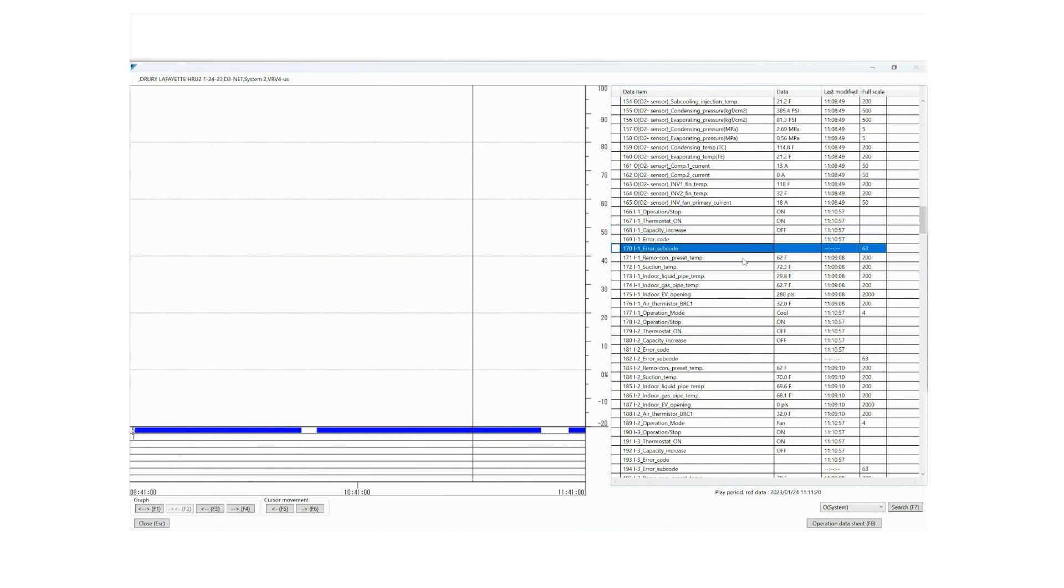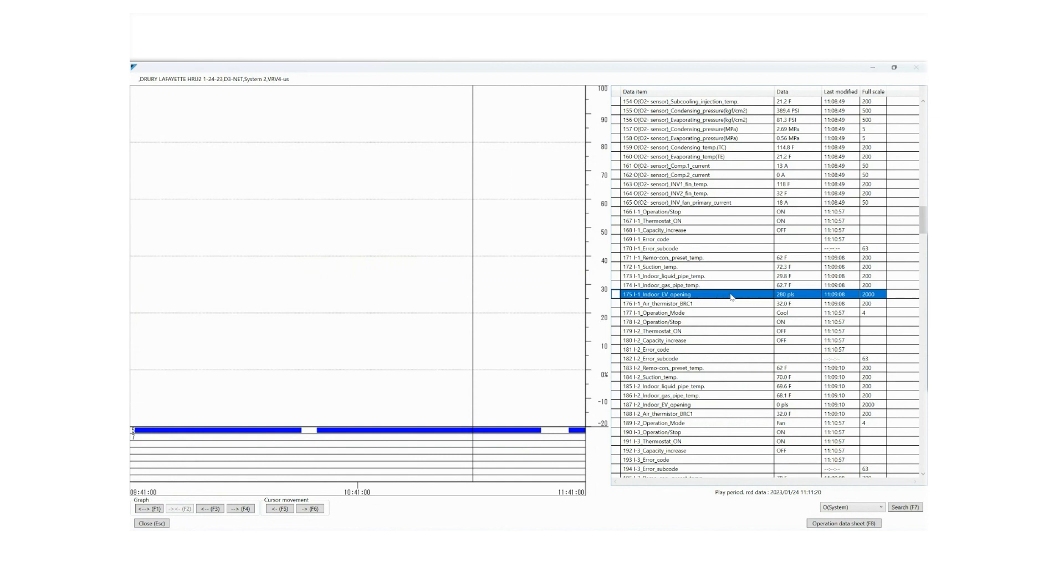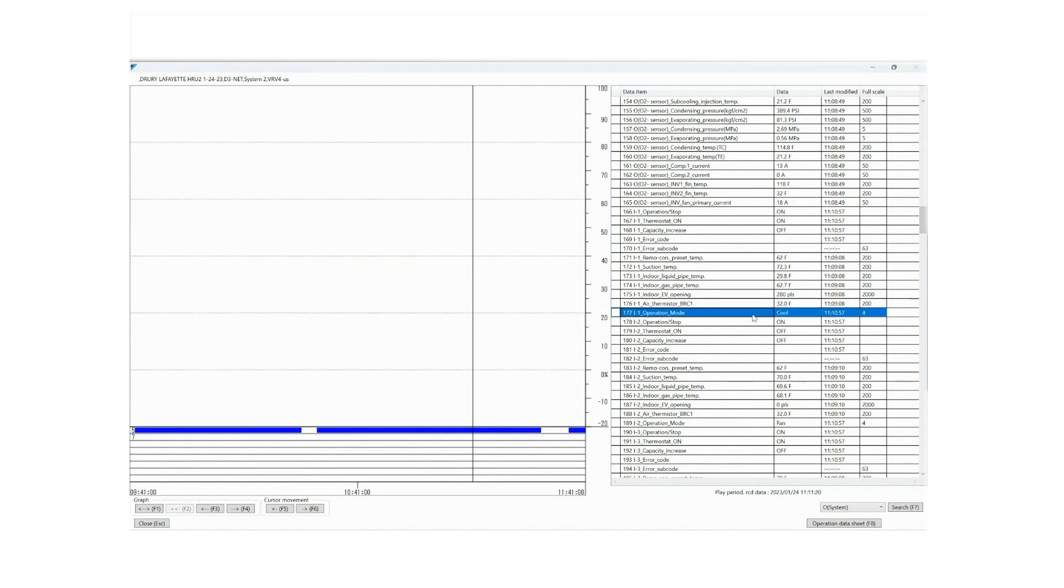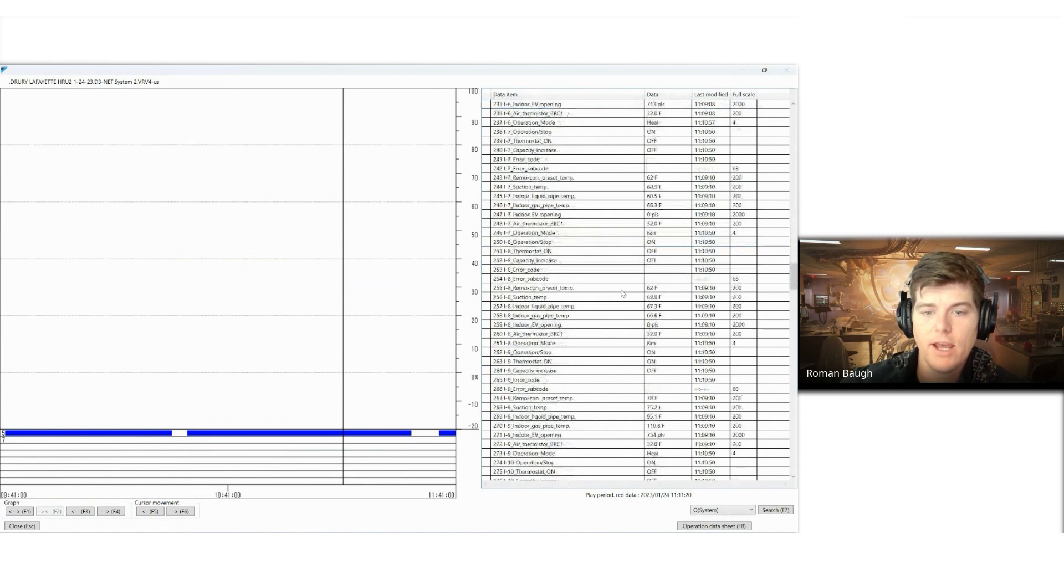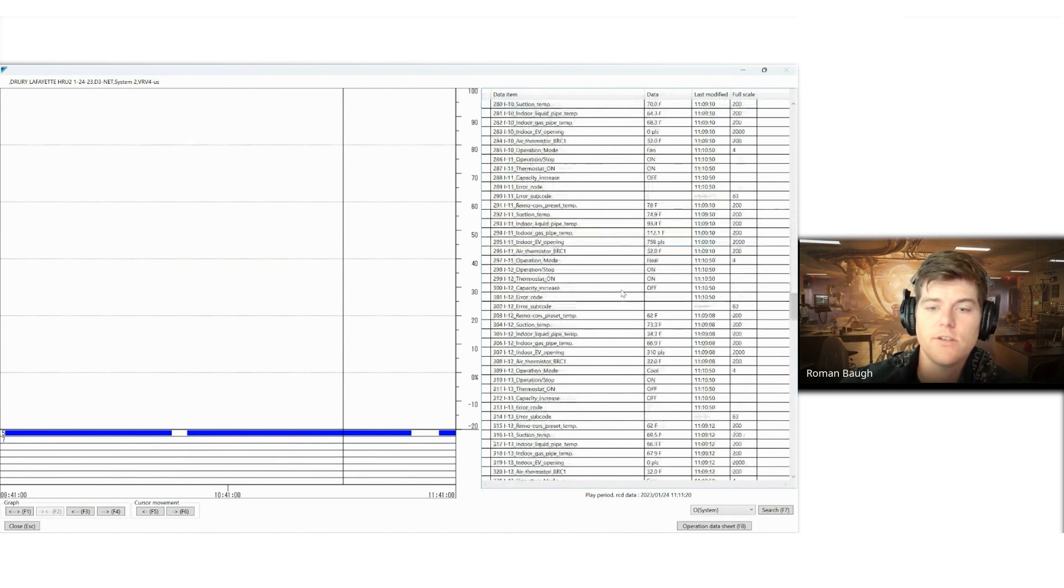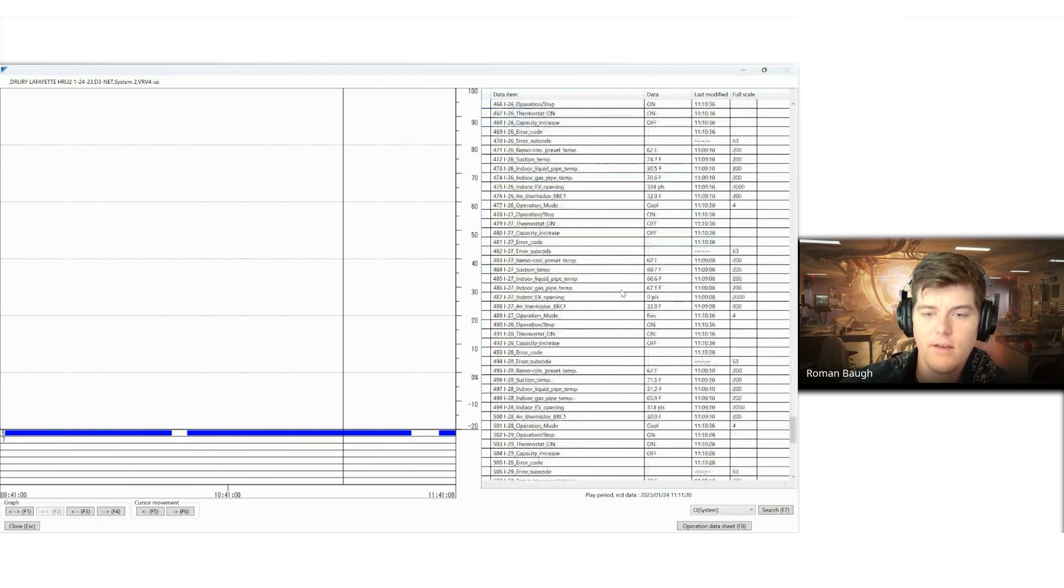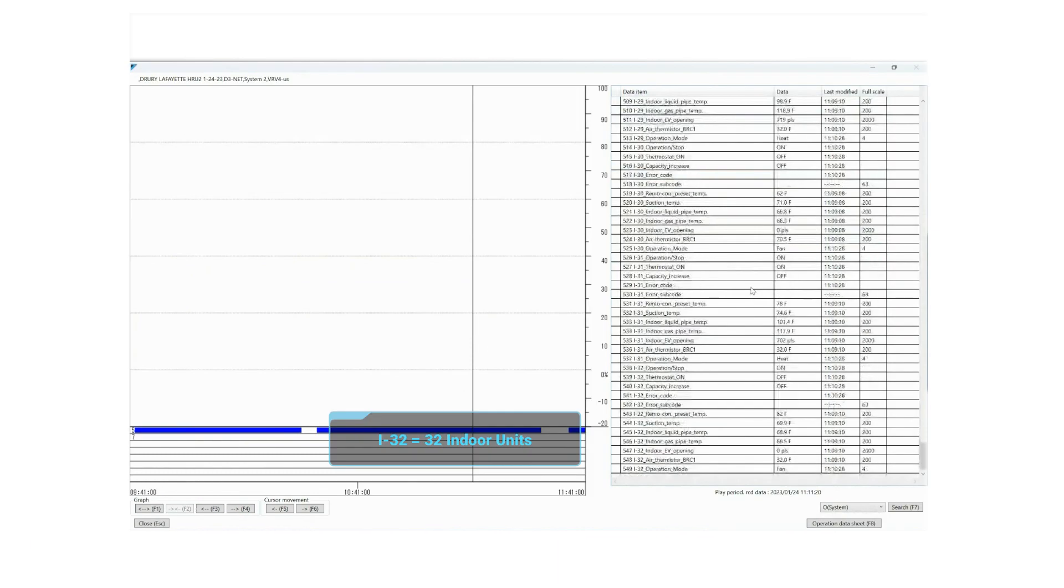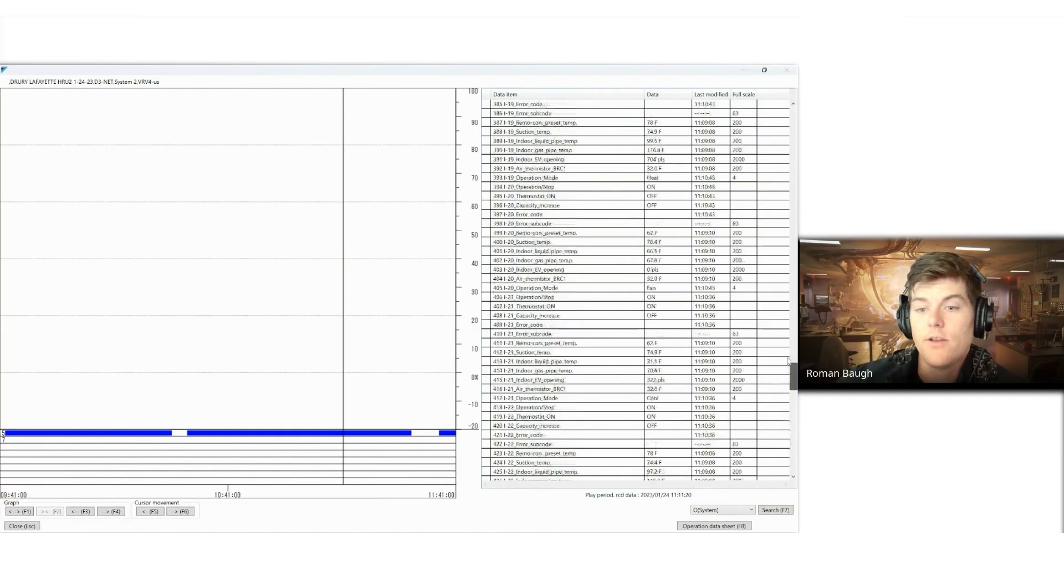Error code, error subcode, remote preset temp, suction temp. This is your return air thermistor, the air being sucked into the back of the unit. Your indoor liquid pipe temp, your indoor gas pipe temp, and then your indoor expansion valve opening pulses. And then you'll notice if it had a VRC attached to it, that it would give you a VRC temperature here. Operation mode, we are in cooling. Operation mode, stop, and stop. And now we're in IDU number two. So you'll see that that repeats all the way down. And so on this system, I can tell you confidently that I have 32 indoor units on this system. I-32 tells me I have 32 indoor units.